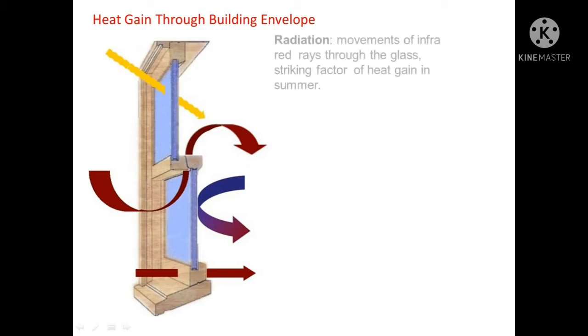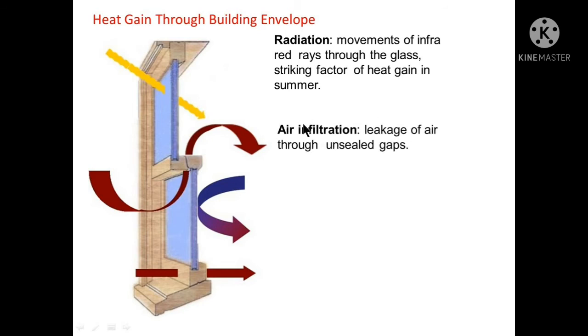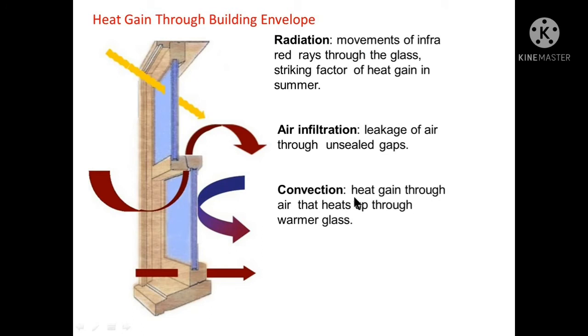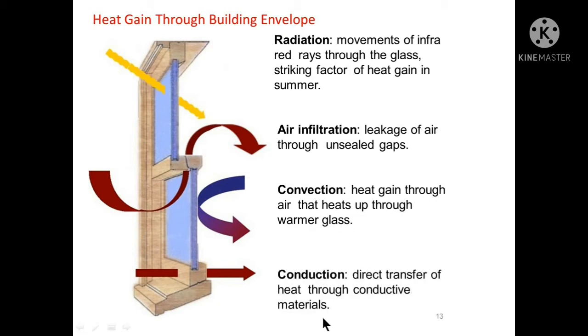The heat gain through building envelopes can be shown in four ways. First is radiation — movement of infrared rays through the glass, which is the main factor of heat gain in summers. Next is air infiltration, that is leakage of air through unsealed gaps. Next is convection — heat gain through air that heats up through warmer glass. Last is conduction, that is direct transfer of heat through conductive materials.